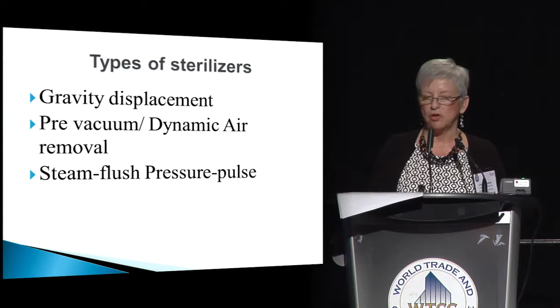Often as an ICP or an MDR manager, we're asked to take part in the purchasing of sterilizers. Before purchasing a steam sterilizer, it's very important to understand the type of sterilizer that is required for the devices being sterilized, the workload, the volume of your cases, the number of sets of instruments that will be required, and the turnaround time. The turnaround time for these sets and different packages is key because there's more than just the sterilization time. As we said, there's the transport, and there are many things to know.